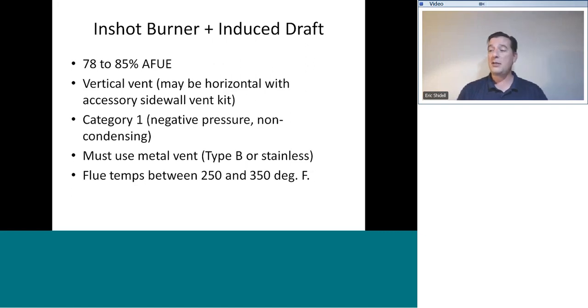Those 78 to 85% AFUE furnaces are also category one, which means the vent is negative pressure and it is non-condensing. You must use a metal vent, type B, or stainless steel, or a flexible, listed, and approved metal flue liner. Flue temps on these products are going to range between 250 and 350 degrees Fahrenheit. Notice that increase in efficiency drops flue temperatures, which is why condensation in the flue is even more of an issue, hence the need for the metal liner to prevent condensation. Also, combined with the fact that there is no dilution air, we've got to prevent condensation in the flue because it's likely to happen unless our vent is constructed to avoid it.